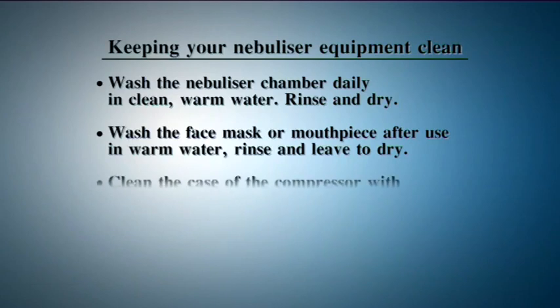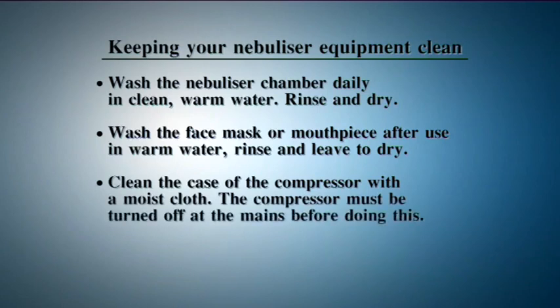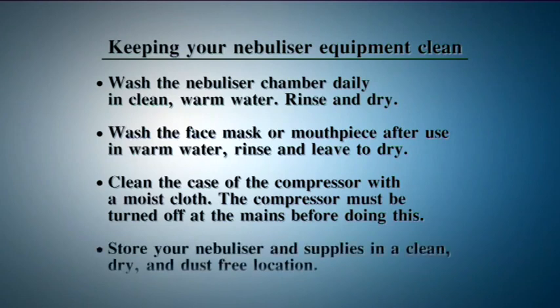Clean the case of the compressor with a moist cloth. The compressor must be turned off at the mains before doing this. Store your nebuliser and supplies in a clean, dry, and dust-free location.